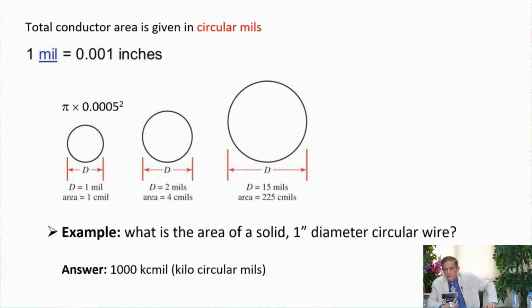If you square this, you will get 1 million. So this wire of 1 inch diameter has an area of 1 million circular mil, or 1,000 kilo circular mil. You have to be familiar with this unit. This is the most used unit in a transmission line, and it's available in tables. Is it clear, the circular mil?